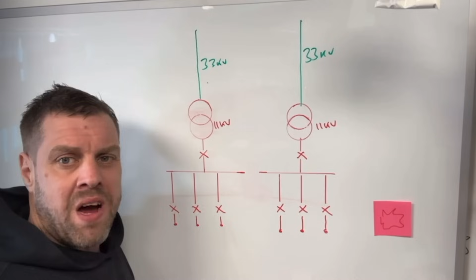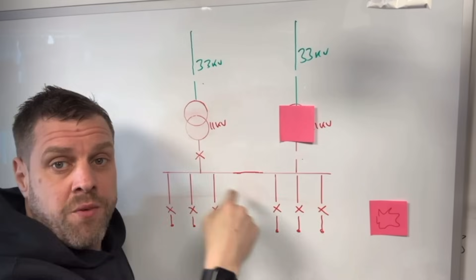Now let's go through the process of switching this transformer out for maintenance without affecting the supply. First, simplified, we close the bus section, so for a temporary period the transformers are feeding all 6 circuits. Then we open that one, and we'd have one on the 33 kV as well. Now that transformer is switched out, and you can operate on it for maintenance while feeding from this one, because both transformers can meet the load on their own.